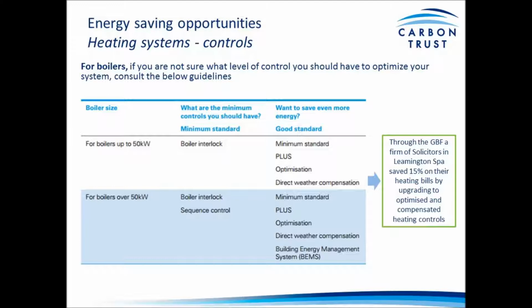For boilers, just a bit of guidance here on what controls you should look to have depending on your boiler size. So for smaller boilers, up to 50 kilowatts, we typically expect as a minimum a boiler interlock with a timer or thermostat. But if you're looking for a good standard, look to implement the optimization and direct weather compensation we discussed on the previous slide, just to optimize the system and its control.